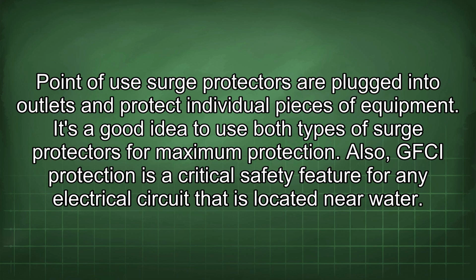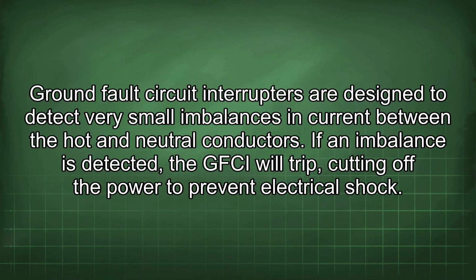Also, GFCI protection is a critical safety feature for any electrical circuit that is located near water. Ground fault circuit interrupters are designed to detect very small imbalances in current between the hot and neutral conductors. If an imbalance is detected, the GFCI will trip, cutting off the power to prevent electrical shock.